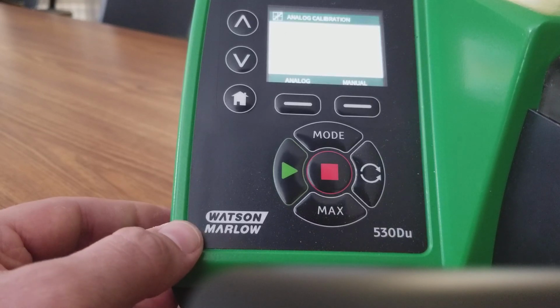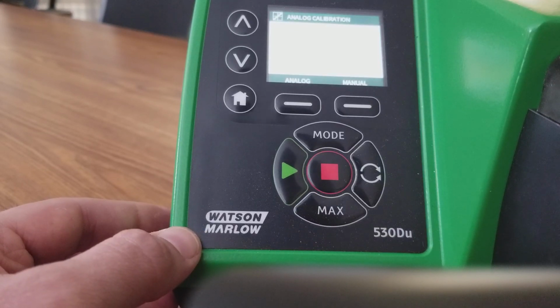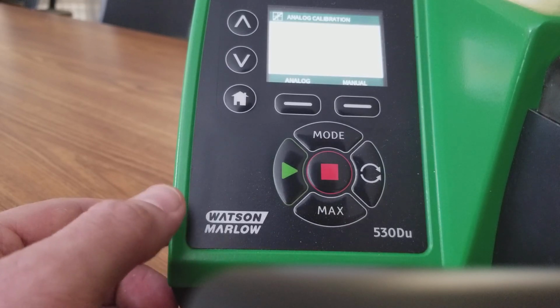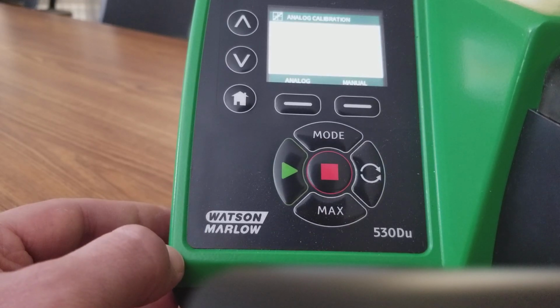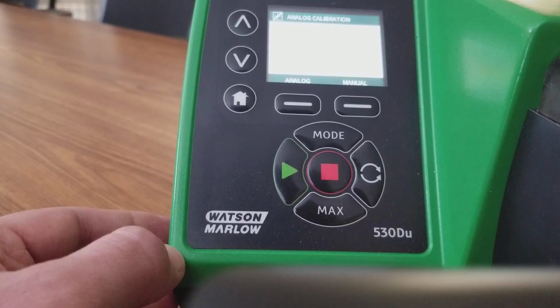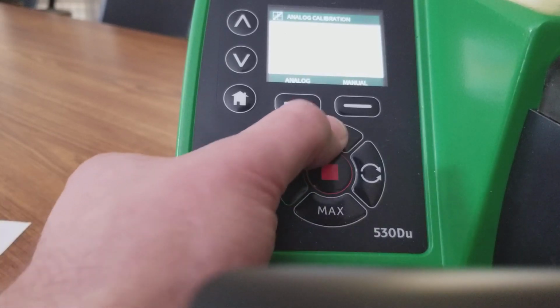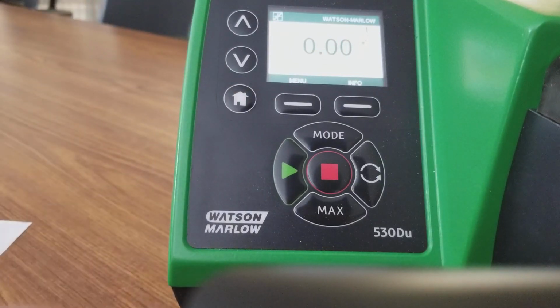We just basically have to figure out how many gallons per hour you would need at your 20 milliamp setting, set that in under your percentage, and now it's linear with your parts per million anywhere with the flow of that plant. At this time, you would be able to select your analog, and then you'd be operating off of SCADA. That is all. Thanks.